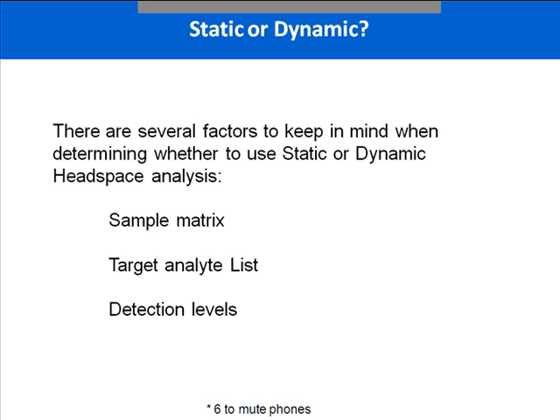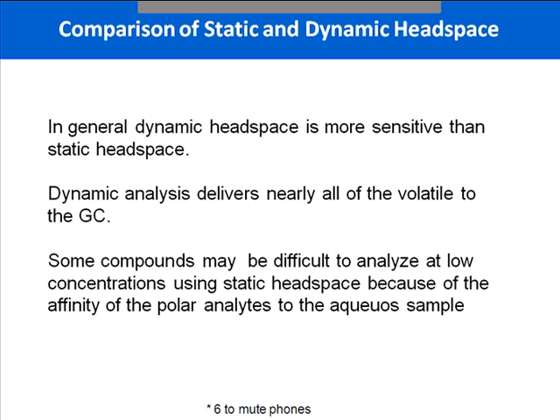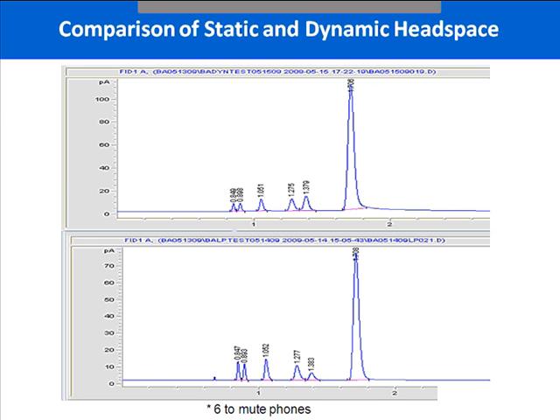There are several factors to keep in mind when determining when to use static or dynamic headspace analysis: the sample matrix, the target analyte list, and the detection limits. In general, dynamic headspace is more sensitive than static. Dynamic delivers nearly all the volatiles to the GC. Some compounds may be difficult to analyze at low concentrations using static because of the affinity of polar analytes to the aqueous sample. In closing, this is a comparison of the static and dynamic headspace results for blood alcohol. The top chromatogram is a dynamic analysis using the trap method for blood alcohols on a BAC1 column. The bottom is a static analysis using the same BAC1 column. Both indicate good chromatography, while the dynamic mode presents lower detection limit capabilities.